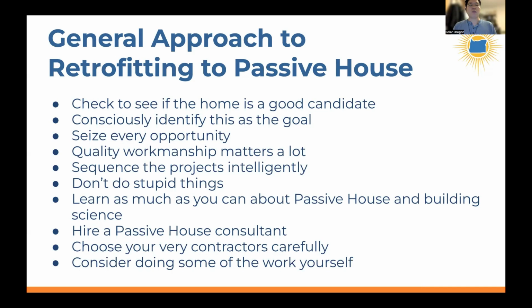Even if your HVAC contractor tells you that you need a 3 ton heat pump, you can have that conversation with them and say, no, I will in the next 1 to 2 years do a bunch of envelope work on my house, or hire somebody to do that work, and reduce my loads down to needing only about a 1.5 ton heat pump. Then help the HVAC contractor understand why you'd want that.